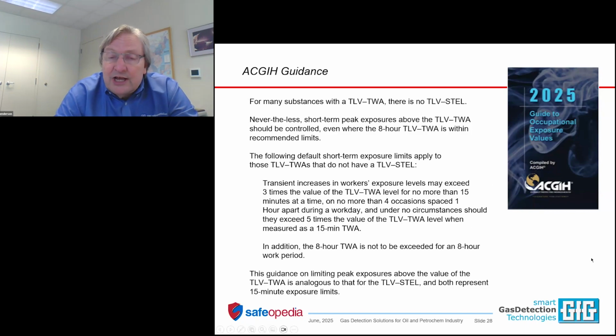Now, this is a lot of words in this slide. I don't like slides with a lot of words, but the words in the case of this slide come directly from the TLV guide published by the ACGIH. Those are the folks, the American Conference of Governmental Industrial Hygienists. These are the guys that come up with the TLV recommendations. And right from the book, it explains the science behind the TLV and how to set the alarms. The TLV doesn't tell you where to set the alarms. It gives you a maximum recommended exposure limit. In the case of the benzene TLV, it's a one-part definition. It's an 8-hour time-weighted average of 0.02.